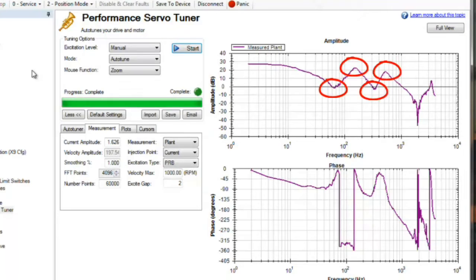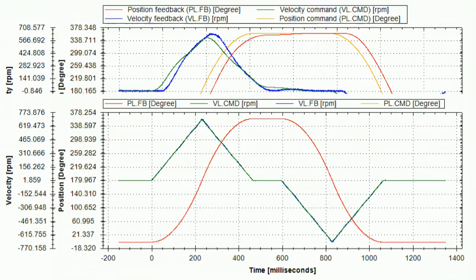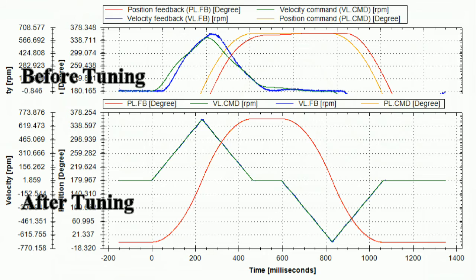Returning to the scope, we captured the same move as previously recorded. Looking at the before and after, the effects of the performance servo tuner can be clearly seen in the results. Keep in mind this is a two-stage belt system with an inertia ratio of 50 to 1.